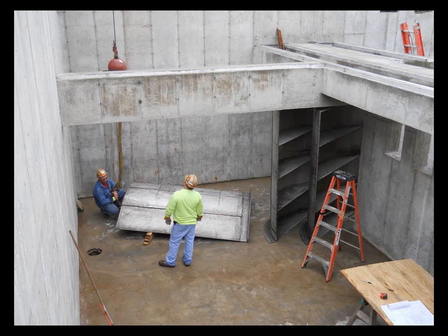So we had to build weirs in behind, and after the weirs, water is discharged over the weirs, it goes through these turning vanes you see the guys are starting to install. This eliminates any dead corners, it eliminates algae growth in the corners, which also has been talked about, and moves the water, speeds it along over into our Parshall flume. Eliminates all the dead spots in the structure.